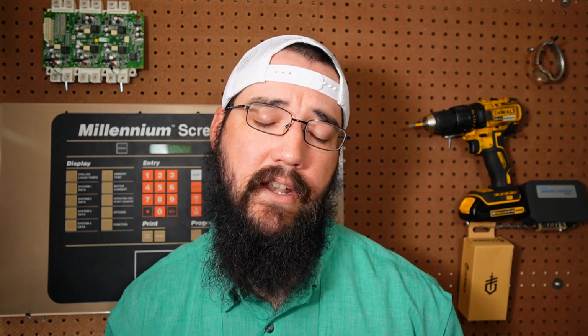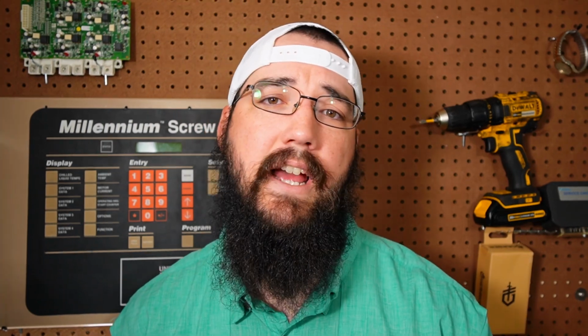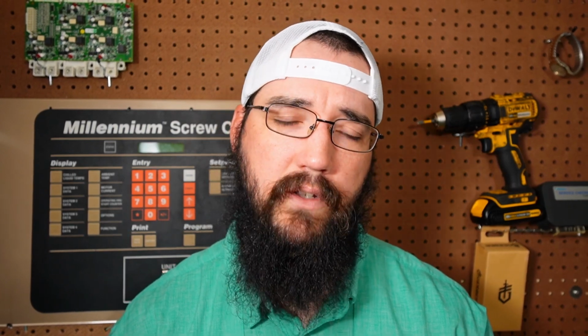Having a gauge at the pump connected in whatever way you can is one thing that's great about the TES 8. It's got a 1/4-inch port right there at the pump, so it's real easy to hook up on its little manifold tree. You don't have to do it that way, just somewhere at the pump. You want to see what the pump's physical microns are, and having that as a comparison to the system microns will help you understand: okay, I'm still pulling at the pump and I just need to be patient, or hey, my pump is starting to stall out because I have an oil issue.